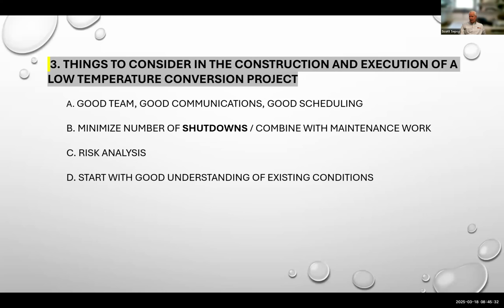Risk. Even though you looked at risk during design, take another look. If shutdowns are going to take too long, you may need temporary systems. Or do you really have N+1? Does your backup pump really work? Equipment lead times are important. Release equipment that you need early, get good submittal reviews, and schedule startup technicians early and get their commitments. The easiest transition is just flipping a valve, so set it up for that future scenario if you can. Try to put freeze pumps and distribution pumps on standby power, as I've said. Failure modes, you have to think of what happens. Schedule the time of year. That's a risk too. You want everything in place and tested before the seasons or the building demand changes. For us, most buildings need to be ready for winter by mid-October. For dormitories, it's late August when domestic water availability is critical. And if you can't finish it based on the schedule, then you're going to have to face the work differently.